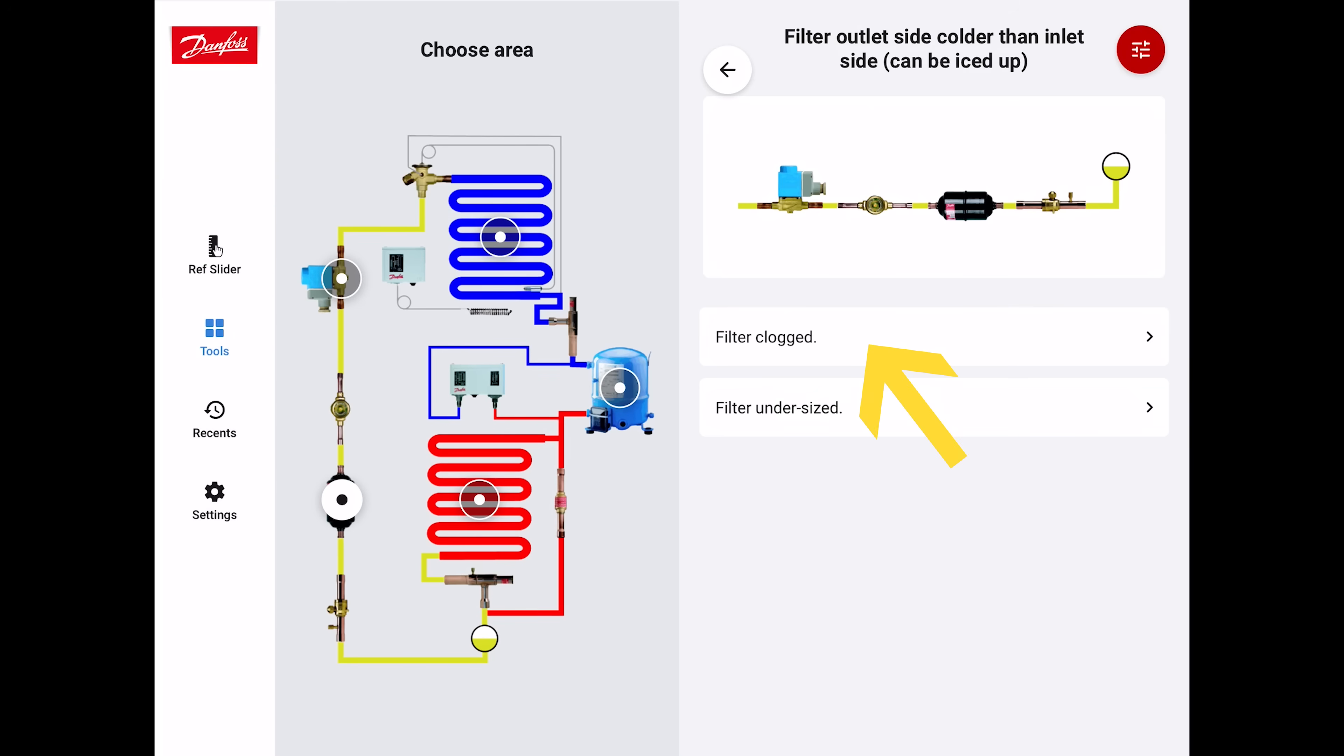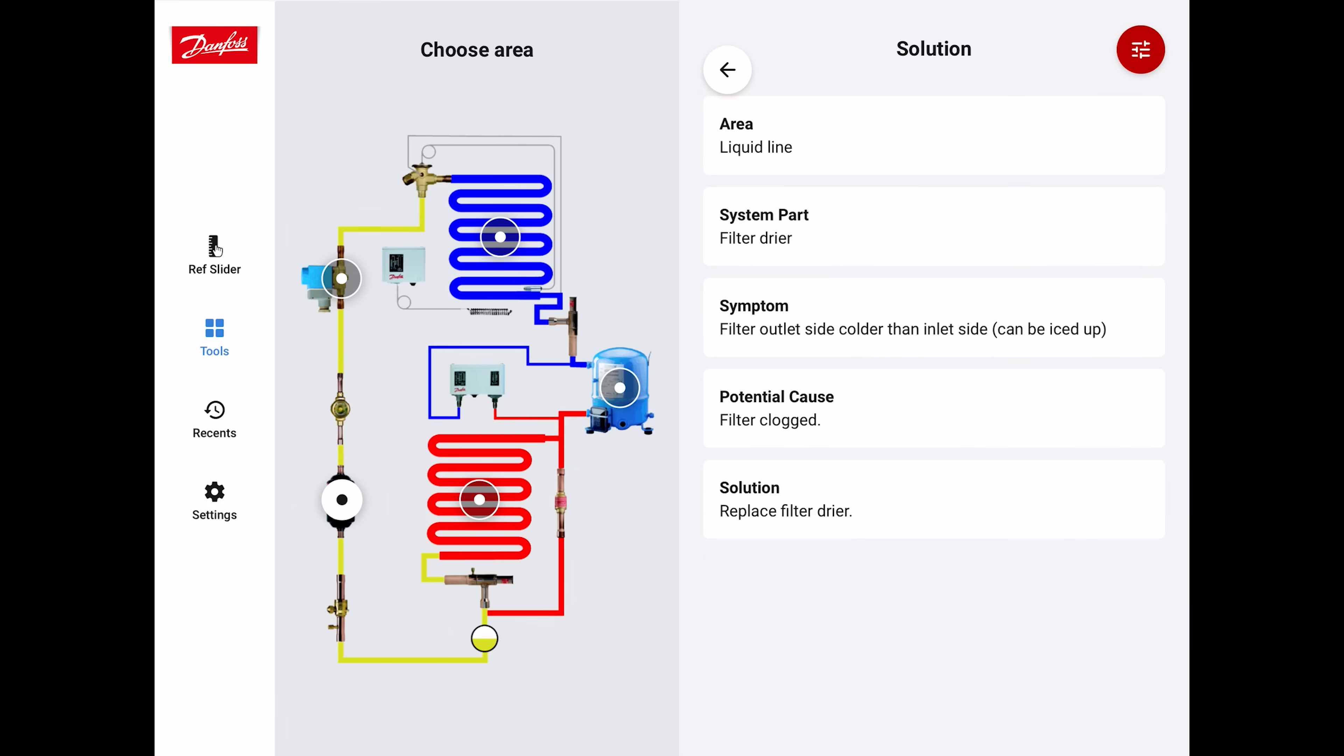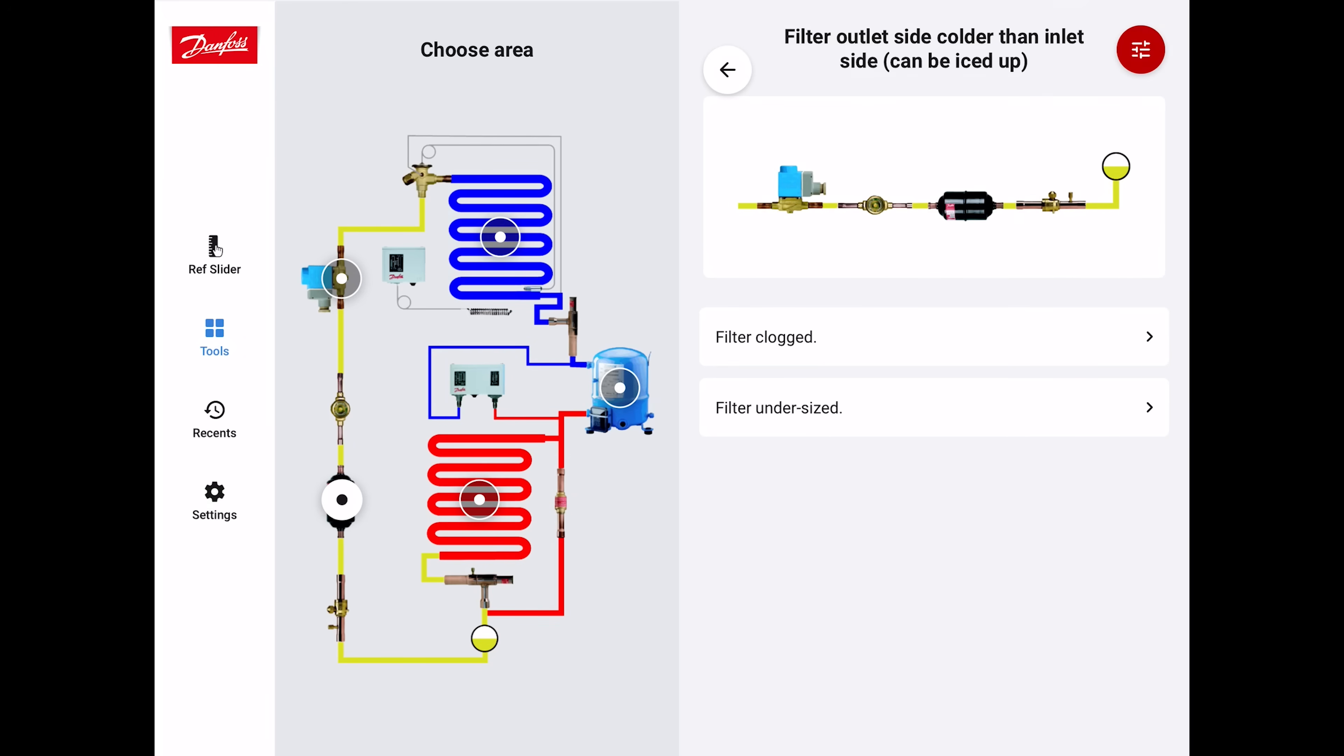It's saying the filter dryer is clogged or the filter dryer is undersized, meaning that there's a restriction in there. You have a pressure drop. Anytime you have a pressure drop, then temperature drops. Let's go to filter clogged. It says area is on the liquid line. System part is the filter dryer. The symptom is it's iced up. The possible cause is filter clogged, replace the filter dryer. That's the solution. It makes it very simple there.